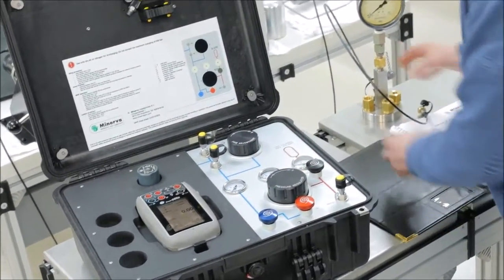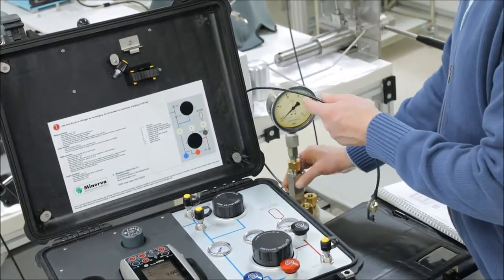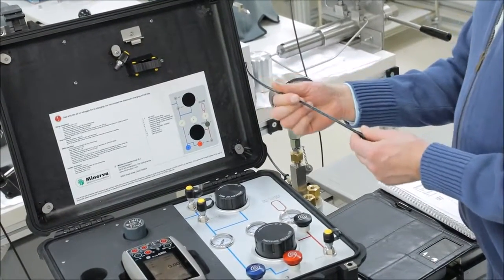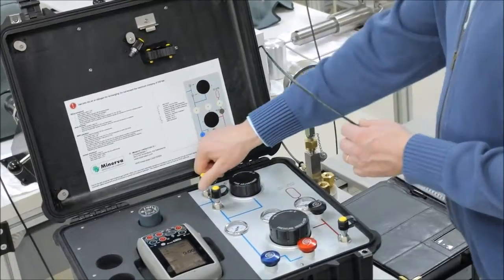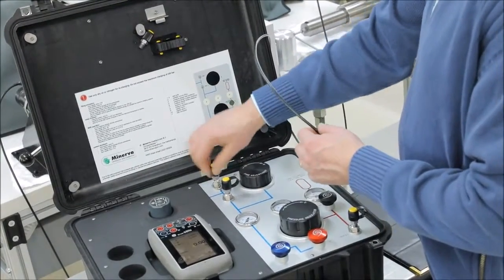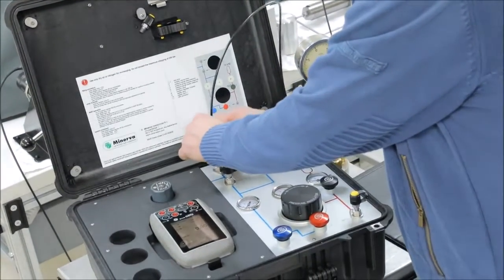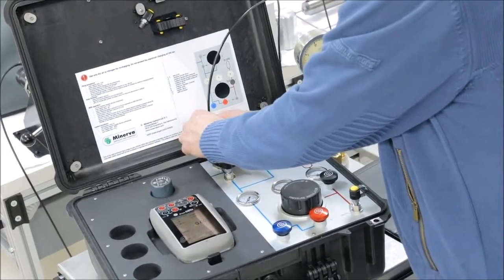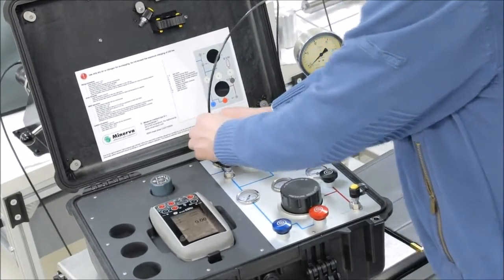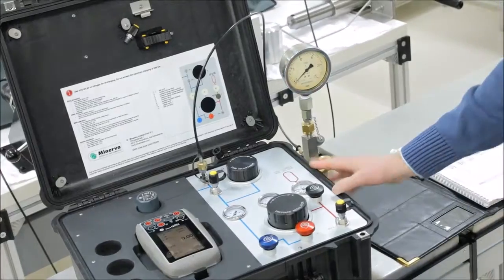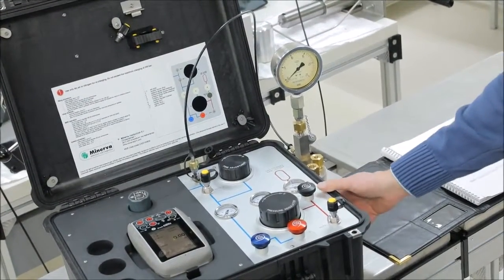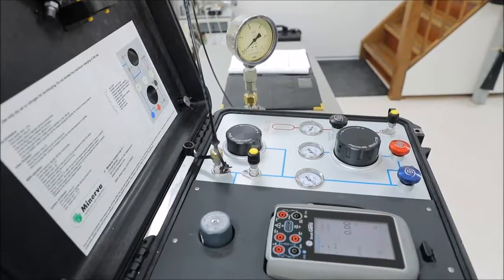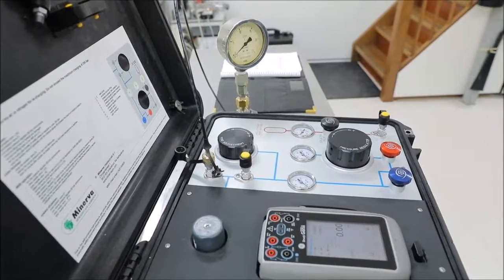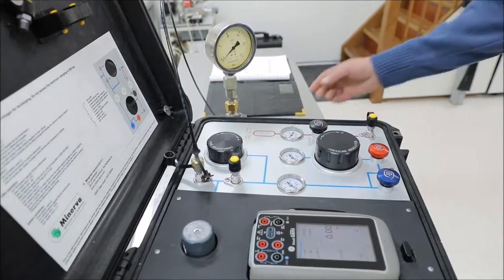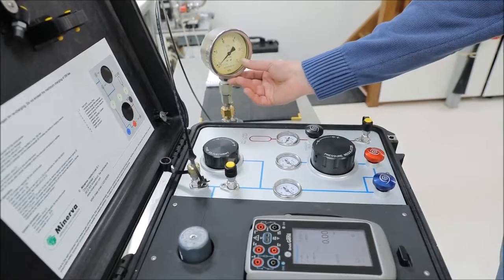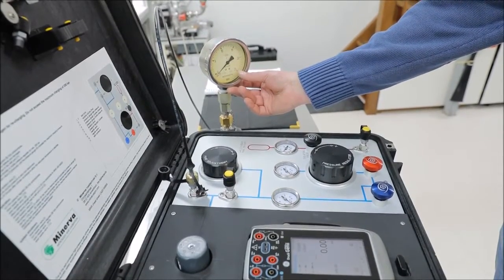Next we're going to connect my device under test, the analog gauge, by means of a high pressure flex tube. After doing this, we're good to go. Before starting the actual calibration, we're going to perform a leak test. A leak test is performed by applying a pressure slightly higher than the maximum pressure of my device under test.